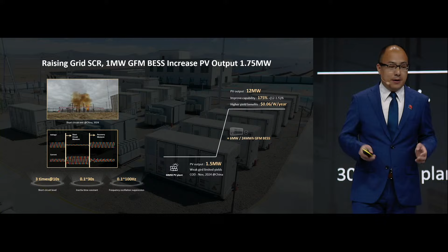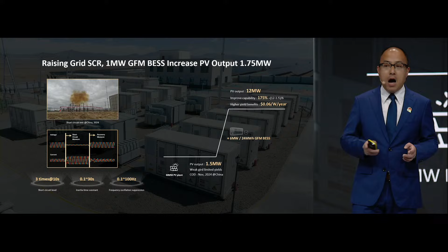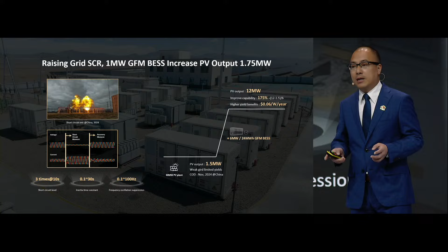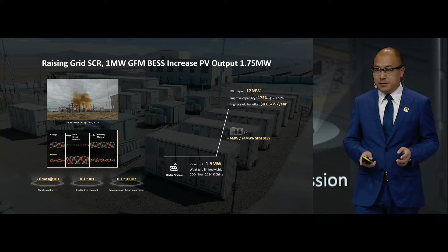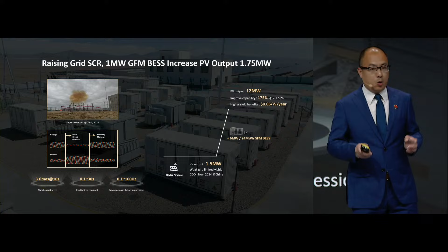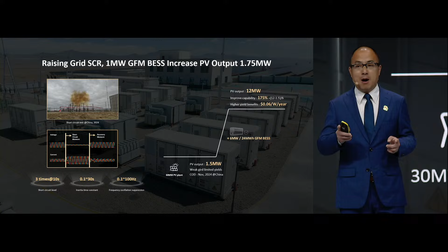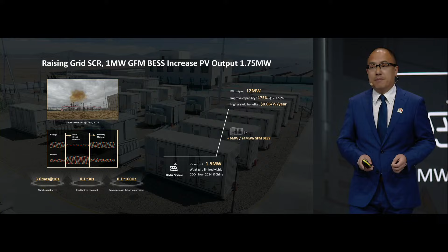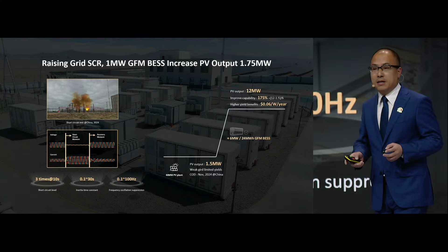Meanwhile, for this plant built in 2024, the installed PV capacity is 30 megawatts. However, due to the weak grid, the PV output was limited to 1.5 megawatts. After the customer installed a Huawei 6 megawatt, 24 megawatt-hour grid-forming BESS, the solution can stabilize the grid, and the PV output can be increased to 12 megawatts. This means 1 megawatt of grid-forming BESS can increase 1.75 megawatts of PV. At the same time, it brought more revenue to the customer, earning an additional 6 cents per watt per year.